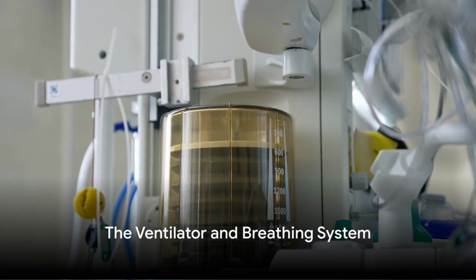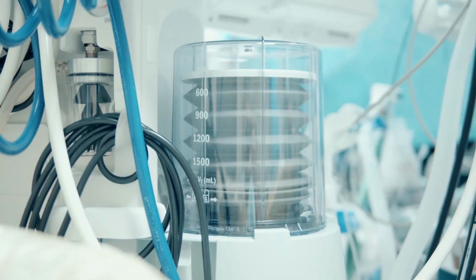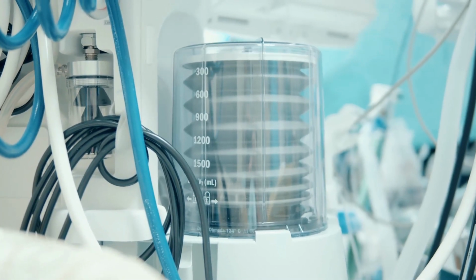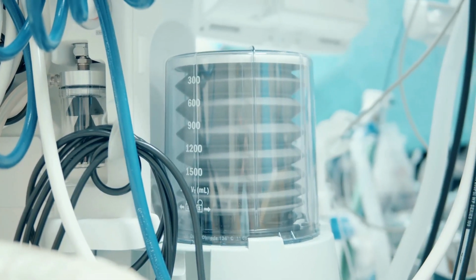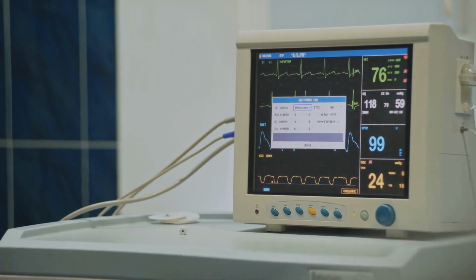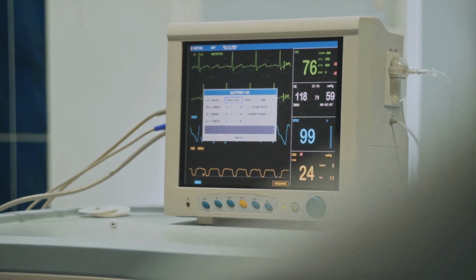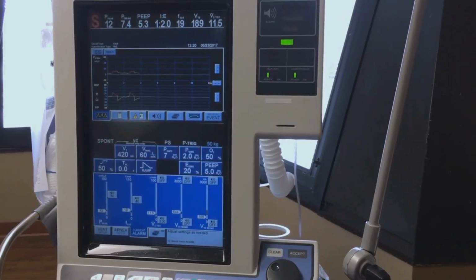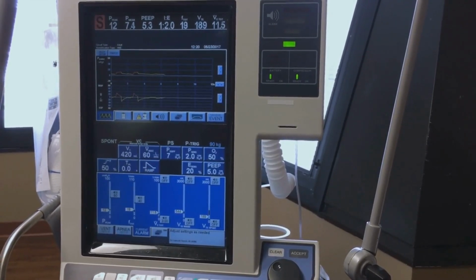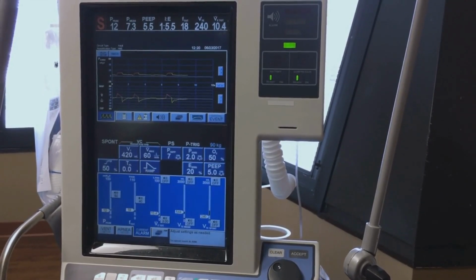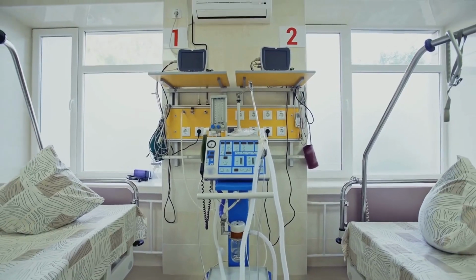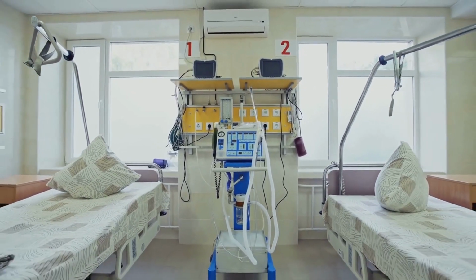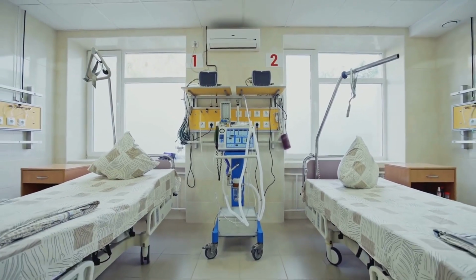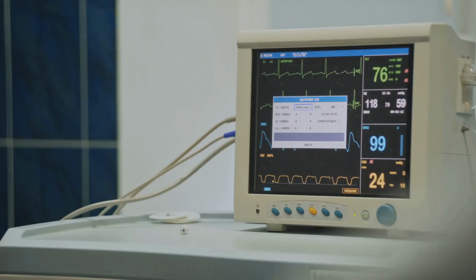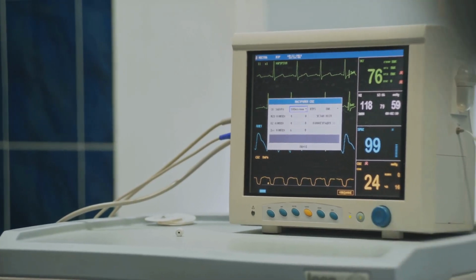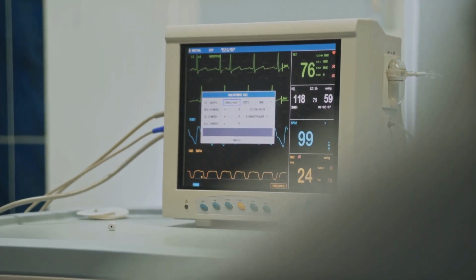Now, we'll explore the ventilator and breathing system. Let's dive right in. The ventilator and breathing system are the unsung heroes of the anesthesia machine. They're the lifelines that ensure a patient keeps breathing, even when under the heavy influence of anesthetics. The ventilator is a mechanical device that replaces or supplements the patient's natural breathing. It generates a flow of gas into the patient's lungs, then allows it to flow out again, simulating the process of breathing. Ventilators have several key components, including a driving gas source, valves to control gas flow, sensors to monitor pressure and volume, and an alarm system to alert the anesthetist to any problems.